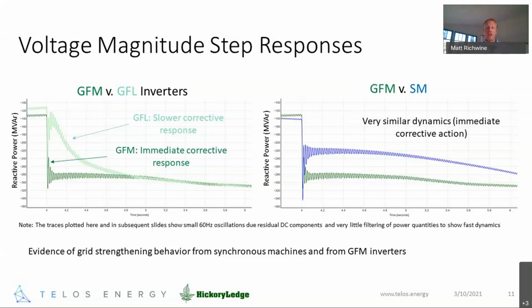Now, if we shift and look over at the grid forming versus the synchronous machine on the right, you see a couple of things. One, they both go down as we expect. Two, the dynamic behavior is actually quite similar. They both immediately jump down to a lower level. And three, the steady state values are different, and we can talk a little bit more about that. That's indicative of the corrective effort that each resource is able to apply more consistently.